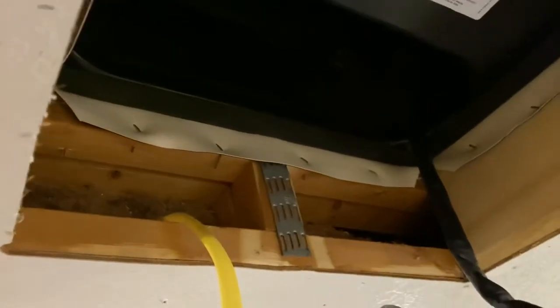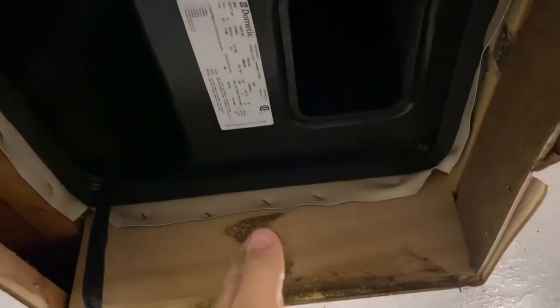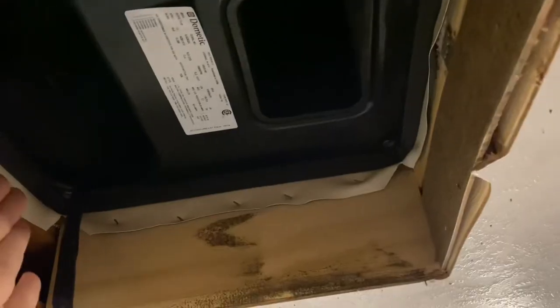This was pretty disappointing when I pulled this down. There was a little bit of tape up inside here, just kind of falling off. I ended up just taking it all down, but you can see it's opened up to the ceiling there. I'm going to try to see if I can cut some foam boards to fit in there and cover these holes up, and also go around the side here, insulate it a little bit better. Then I'll build a baffle in the middle as well, so I can keep the cold air separate from the return air.